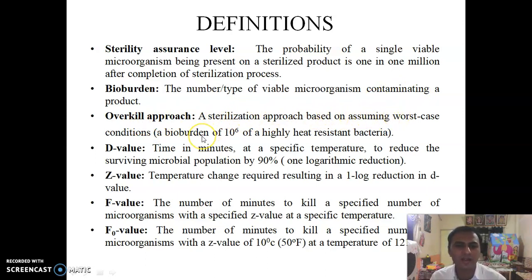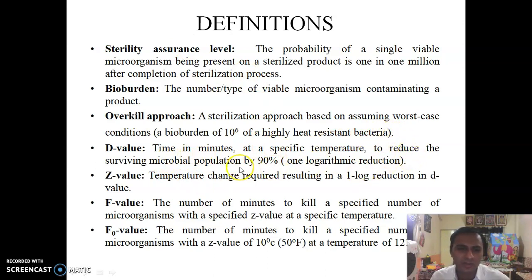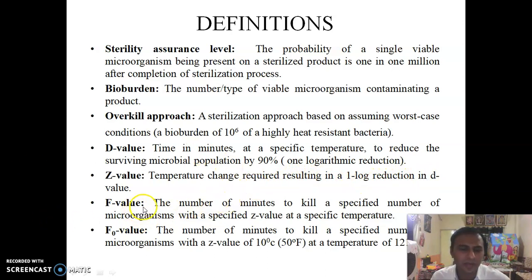The overkill approach assumes a bioburden of 10⁶ of a highly heat-resistant bacteria. D-value: the time in minutes at a specific temperature required to reduce the surviving microbial population by 90%, i.e., one log reduction. Z-value: the temperature change resulting in a one log reduction in D-value. F-value: the number of minutes required to kill a specified number of microorganisms with a specified Z-value at a specific temperature.